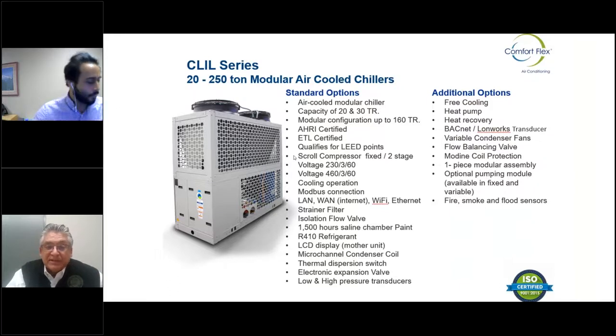So in this case, let's say you had a 75 ton application, you could actually have three 25 ton modules, and then an additional pump package as another module. And then you could have single point wiring to that pump package in all three 25 ton modules. Then if you want to add additional modules down the road, all the way up to 160 ton, you can do that by adding these 30 ton or 25 ton modules.